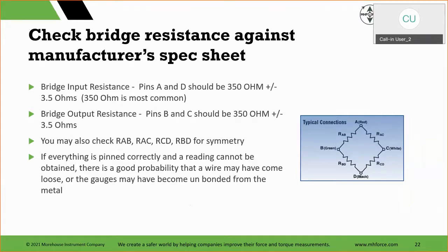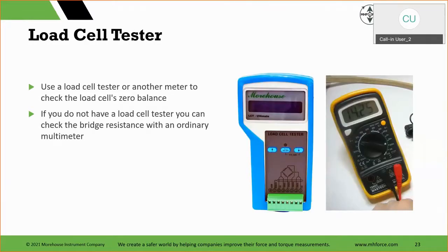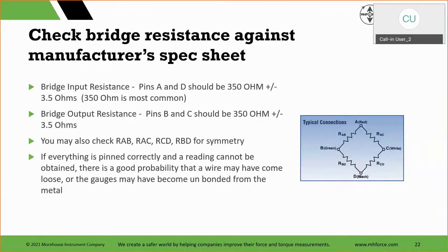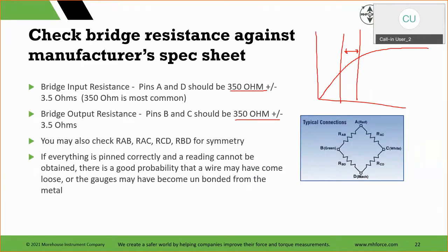Now, the problem with an overloaded load cell is basically Young's modulus. You have your stress-strain curve, and anywhere after a certain point, like here, maybe with the bridge resistance we can still tell, right? With a handheld meter, maybe we get the 360 and the 340. When we get further out here, we can no longer tell. On a handheld meter, it's a really, really small difference that we can actually detect. And then eventually it goes to zero or open when it's too far gone.